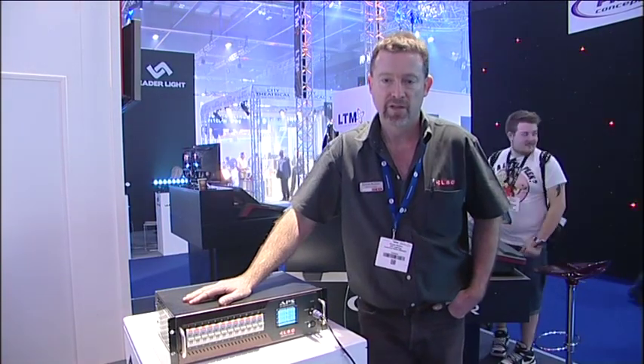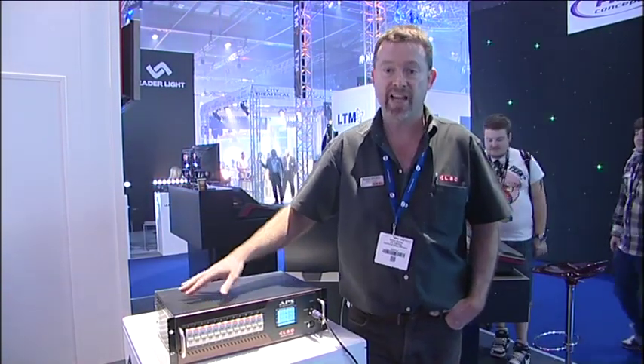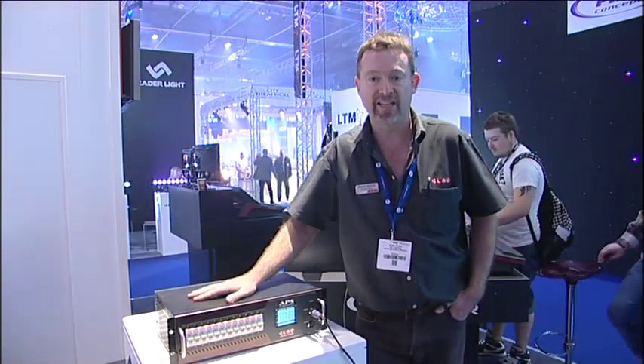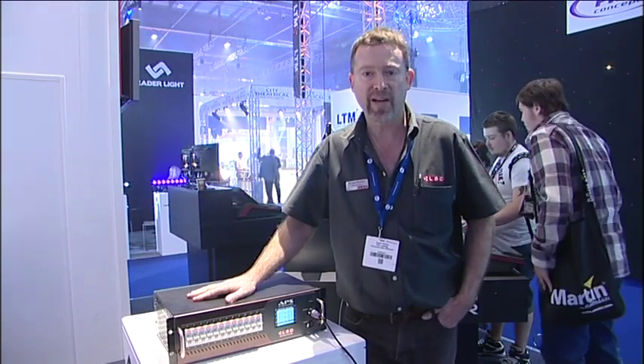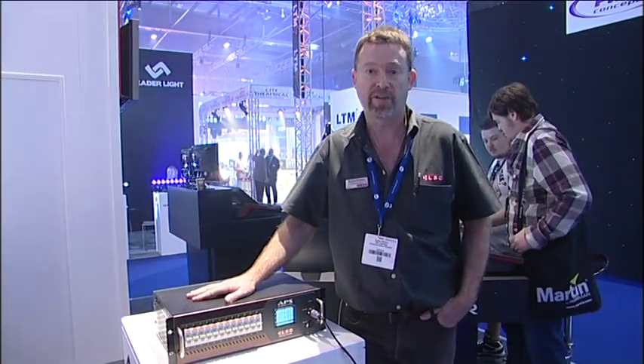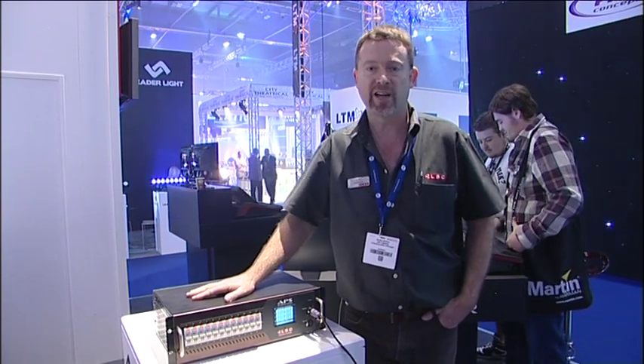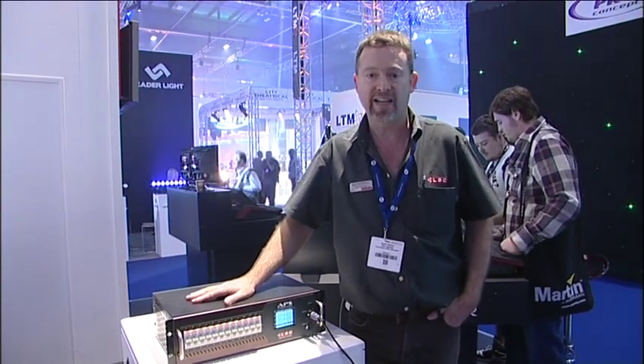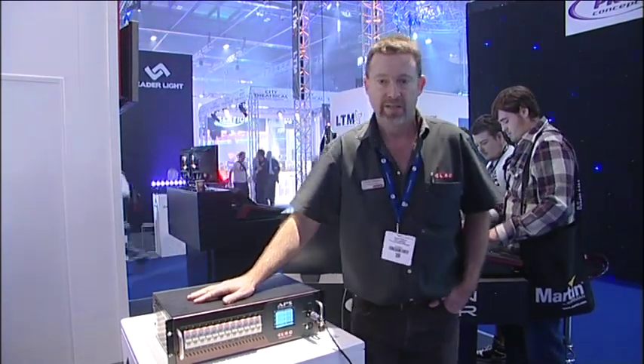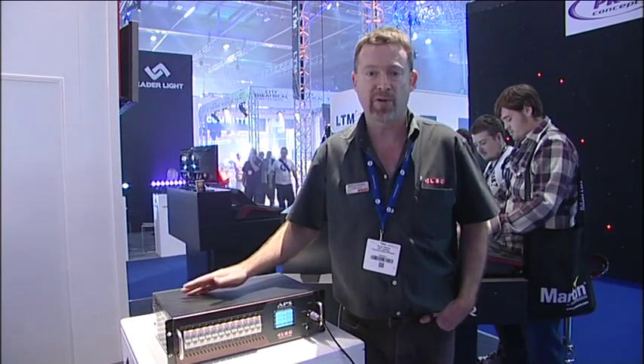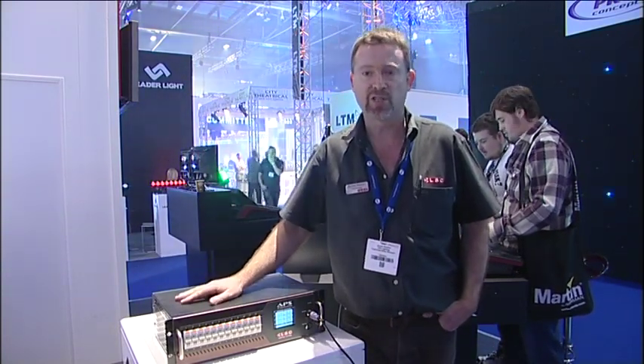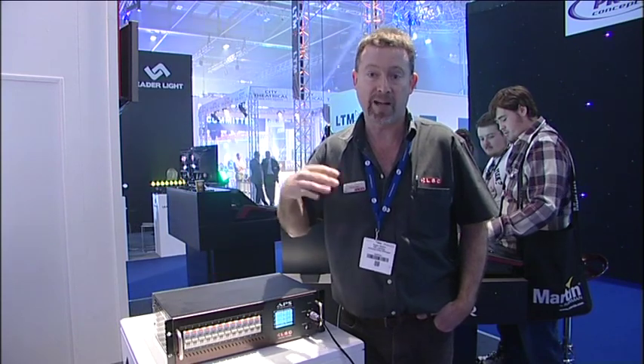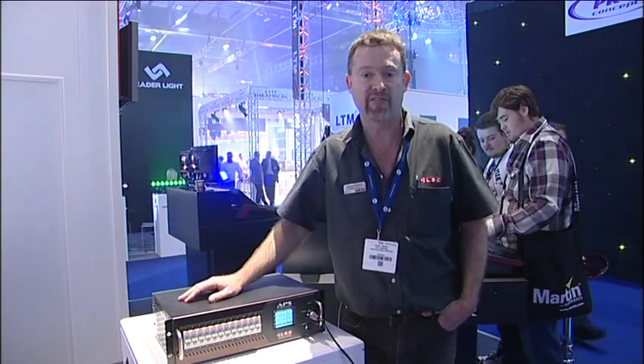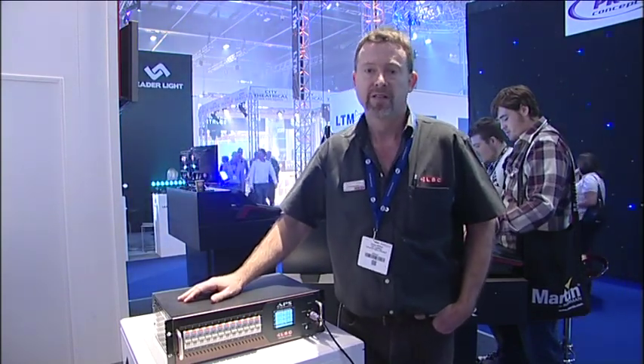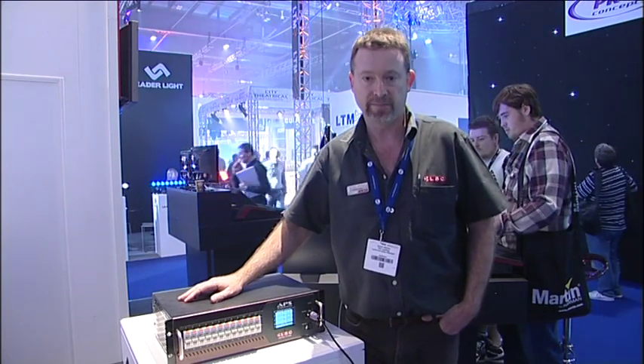distro. The real catalyst for LSC to design the APS was the advent of the modern LED lighting fixture. We saw many venues install these modern energy efficient fixtures only to leave them running 24 hours a day, thus negating the energy savings. Some tried a master switch to turn the units on and off, but this caused problems with tripping upstream circuit breaker protection due to inrush currents. So we designed the APS.